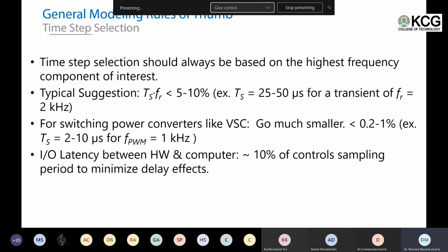Why am I mentioning so much about this? It's very known stuff, but quite often I have seen in many papers where somebody tries to capture a fifth harmonic or 11th harmonic, but they have a time step of 1 micro or 0.1 micro. I also see some papers where they try to capture a load which actually varies at a much lower frequency, or maybe an MPPT, solar MPPT, but the sampling is so high that the algorithm gets confused. So select the time step in accordance to what is your objective.